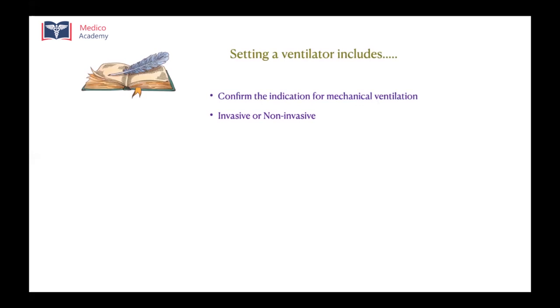So now you have decided you're going to put the patient on invasive or non-invasive support. The first thing that you have to check now is the ventilator connections and circuit. We'll go into detail in the next few slides. So you check the connections and ventilator circuit. Next, you switch on the ventilator and the ventilator will prompt you for a ventilator self-test. Most of the modern critical care ventilators usually go for a ventilator self-test. You can see this in most of the new anesthesia ventilators also.